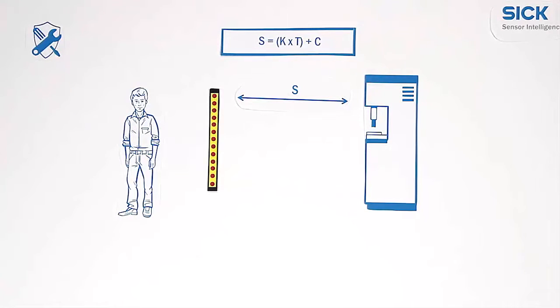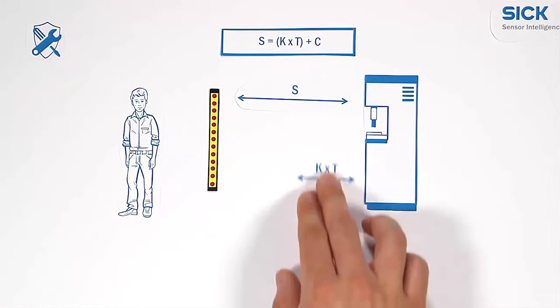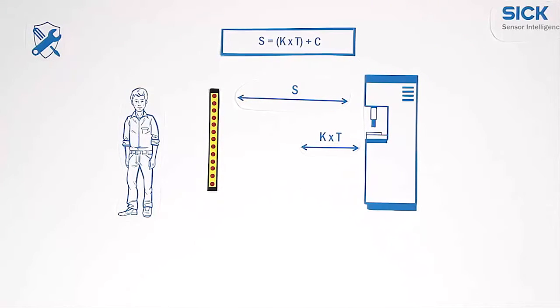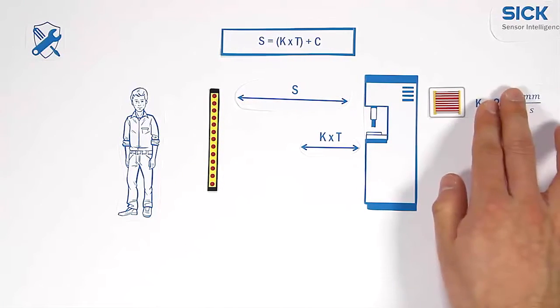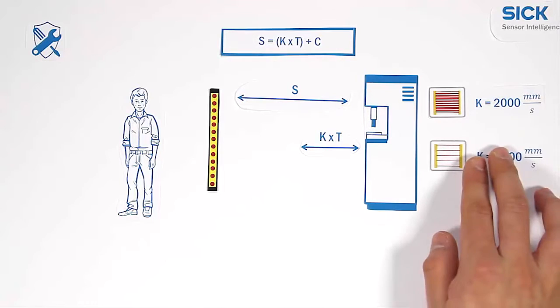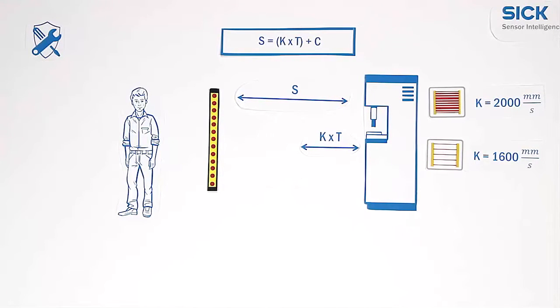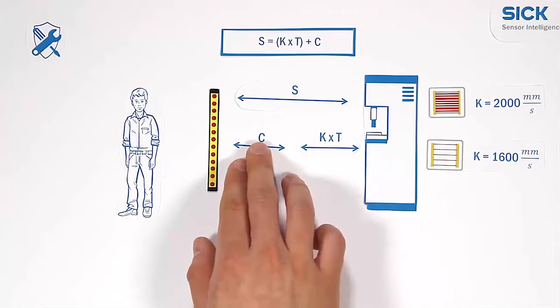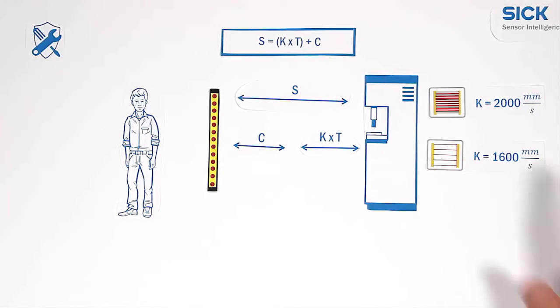The first part of it is the approach speed k multiplied by the stop time of the machine t. In case of light curtains, an approach speed of 2000 mm per second is mostly valid. In the multi-beam case, 1600 mm per second is the correct value. The fixed intrusion distance c has to be added.